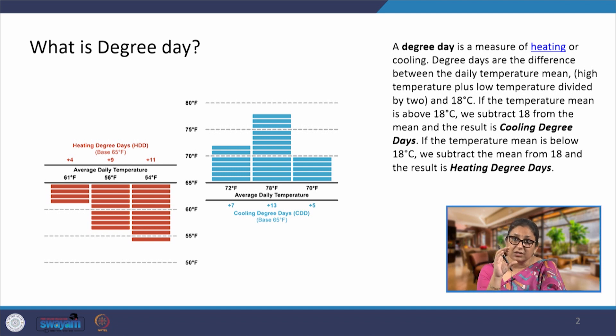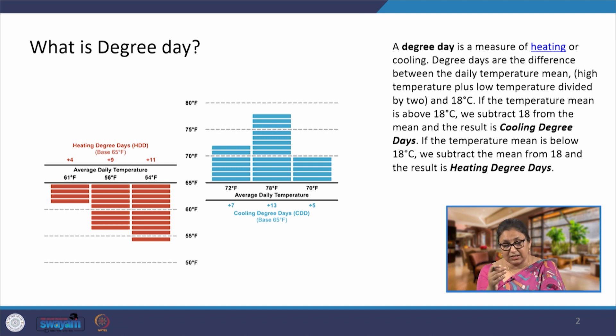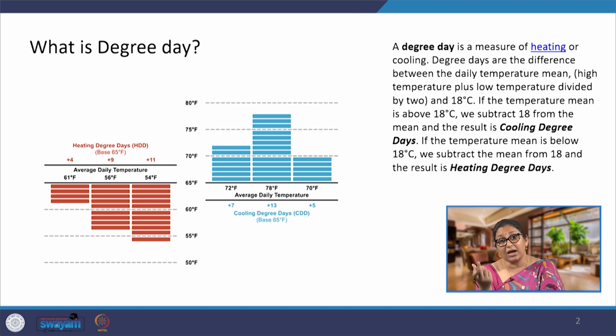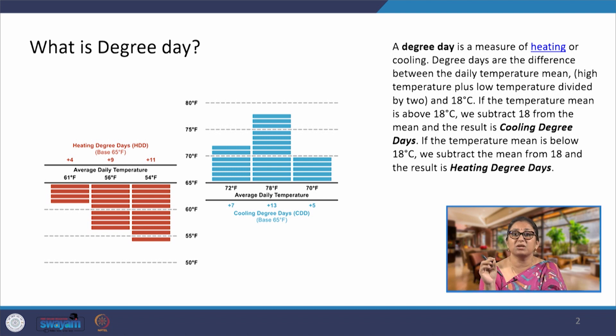For example, if the peak average temperature on a particular day is 28°C, the cooling degree days would be 10. If we take it on an hourly basis: 28 minus 18 equals 10°C for one hour, that is 10 degree-hours. If it remains that for 24 hours, we divide by 24 hours to get the heating or cooling degree day for the day.